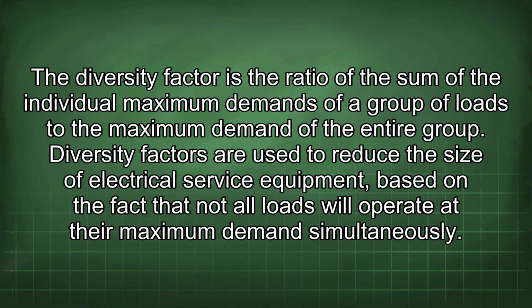The diversity factor is the ratio of the sum of the individual maximum demands of a group of loads to the maximum demand of the entire group. Diversity factors are used to reduce the size of electrical service equipment, based on the fact that not all loads will operate at their maximum demand simultaneously.